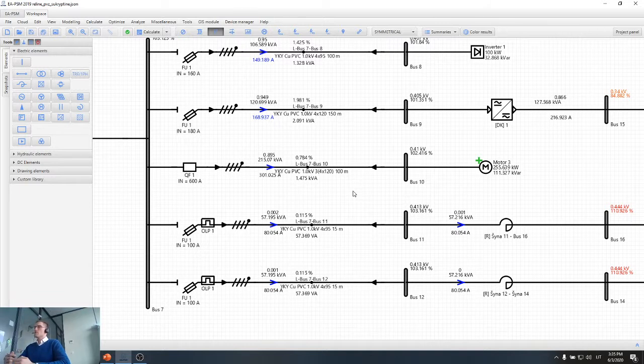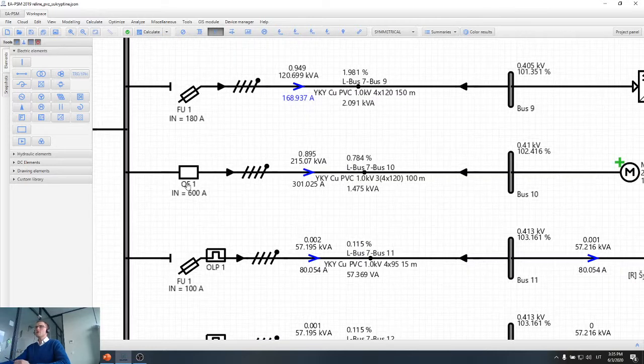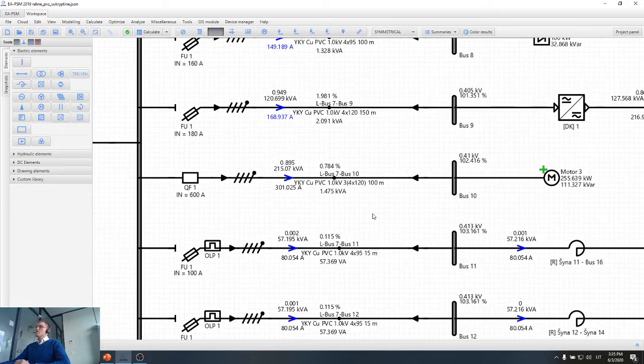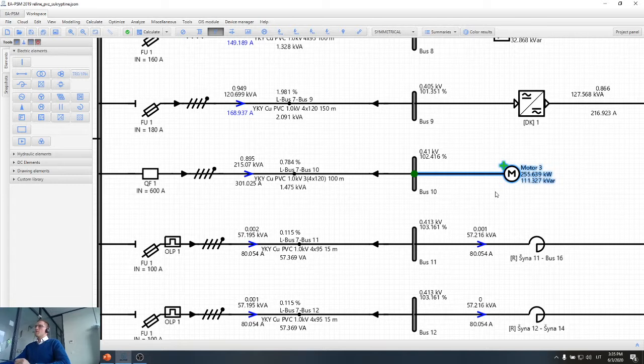But the idea is that short circuit is usually only the result of unsymmetrical operation or overloading of the motor. So when the motor is working for a long time in high temperature conditions, the insulation of the motor starts to degrade, and this causes a short circuit between the windings, and then we have to disconnect that short circuit by using some of the protection devices. So, because we need to protect the motor from the unsymmetrical operation, there are several ways to do that. One of them is negative sequence relays. In an electrical network, we can distinguish several sequences: positive, negative, and zero sequence.